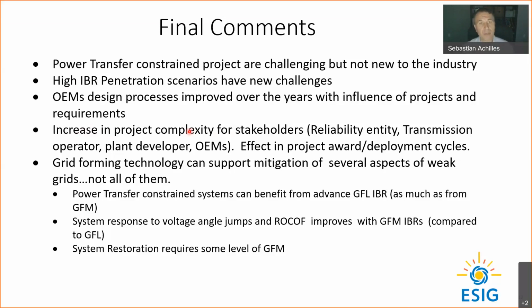Hopefully the industry continues to understand these problems better so that we can address them sooner collectively. I mentioned grid forming earlier. I don't mean to redo this discussion, but I did want to mention that grid forming is a great technology expected to be quite effective for aspects related to rate of change of frequency, voltage angle jumps, or potentially system restoration. The power transfer constraint is not necessarily going to be the main advantage of grid forming though. I think advanced grid following inverter-based resources may have comparable performance in that particular regard.